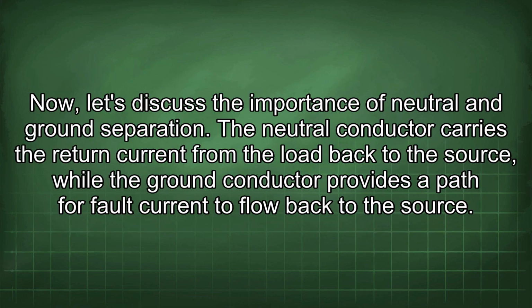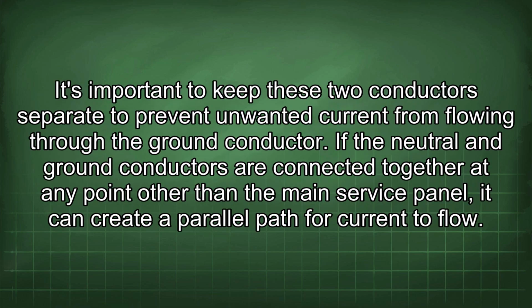Now, let's discuss the importance of neutral and ground separation. The neutral conductor carries the return current from the load back to the source, while the ground conductor provides a path for fault current to flow back to the source. It's important to keep these two conductors separate to prevent unwanted current from flowing through the ground conductor.